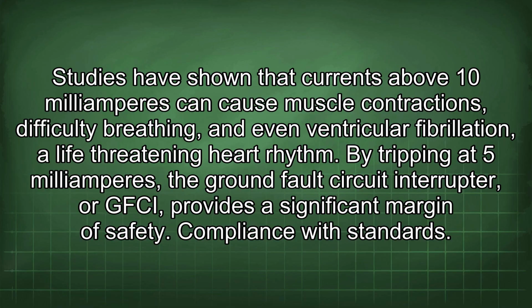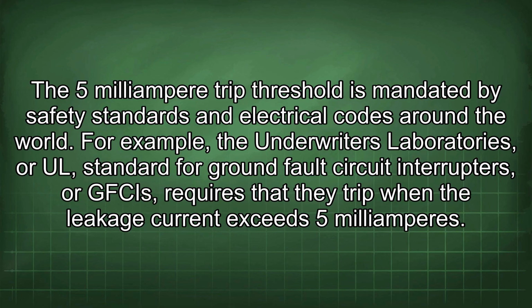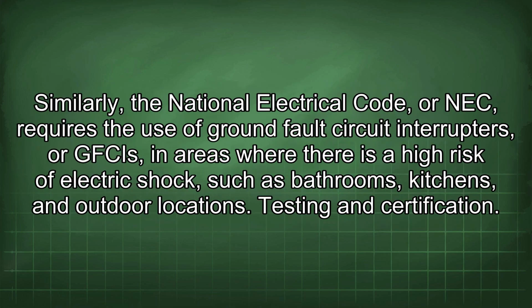Compliance with standards. The 5 mA trip threshold is mandated by safety standards and electrical codes around the world. For example, the Underwriters Laboratories, or UL, standard for GFCIs requires that they trip when the leakage current exceeds 5 mA. Similarly, the National Electrical Code, or NEC, requires the use of GFCIs in areas where there is a high risk of electric shock, such as bathrooms, kitchens, and outdoor locations.